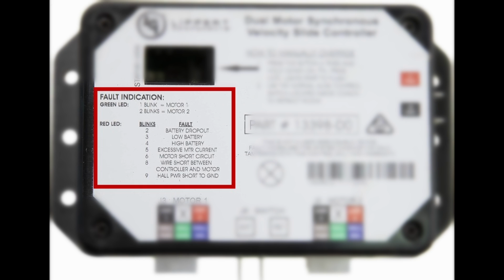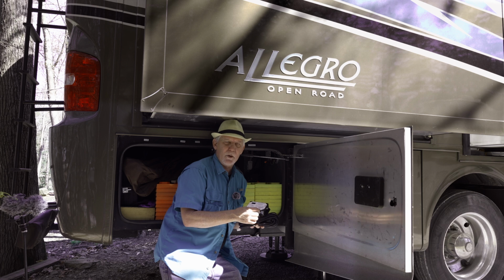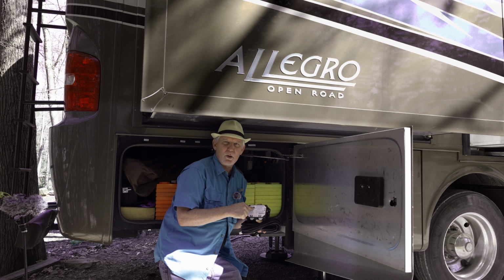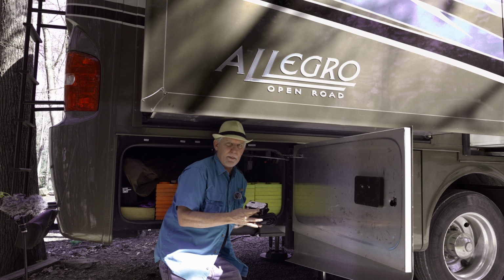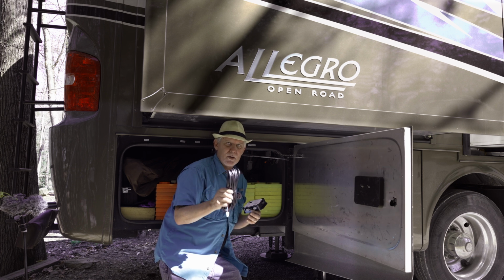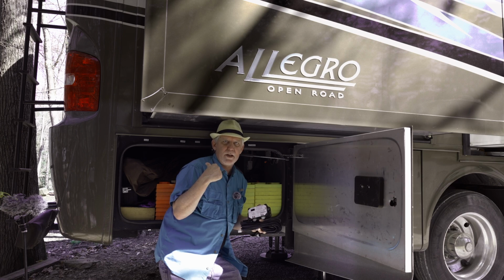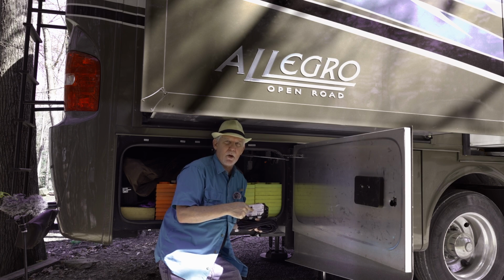By deciding which motor it is—one of the troubleshooting steps we did outside of Savannah, Georgia, was simply switching the wires from motor 1 to motor 2, and the error code still showed motor 1. It showed motor 1 before we switched the wires and motor 1 after we switched the wires. That told us the problem wasn't with the wiring to the motors, and it wasn't the motor itself—it was actually the controller.